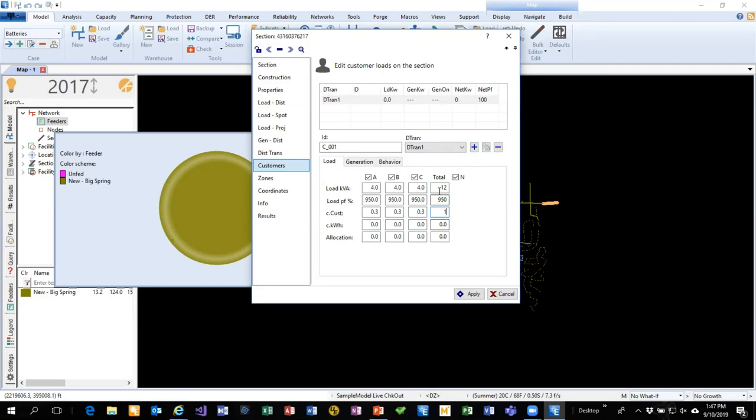The other option, and I think this is the one that we would recommend, is that you have perhaps for a connected customer, you might have, if you're in the UK, it might be 125 customers for 250 kVA. So that's not typical of the US. But certainly is typical of some systems. I guess yours is going to be somewhere between one and a dozen, perhaps. Perhaps occasionally you may have a main that might supply 20 or 30 customers. So that would be the aggregated customer, a load customer that we can apply.